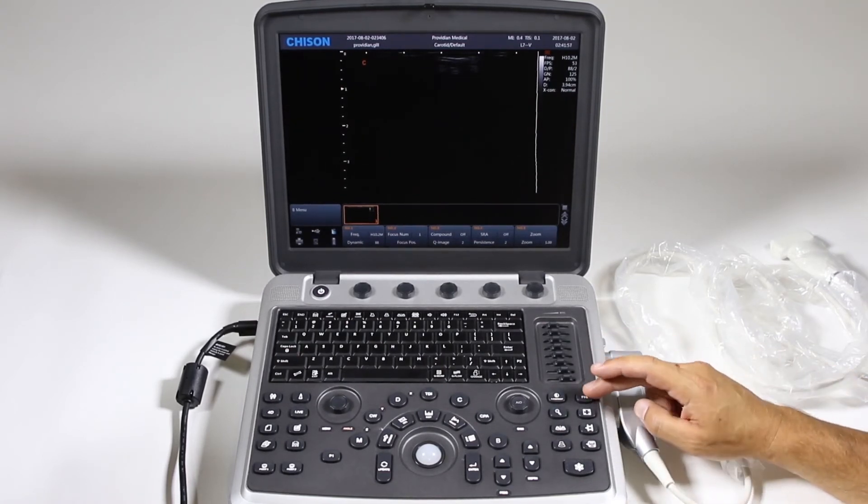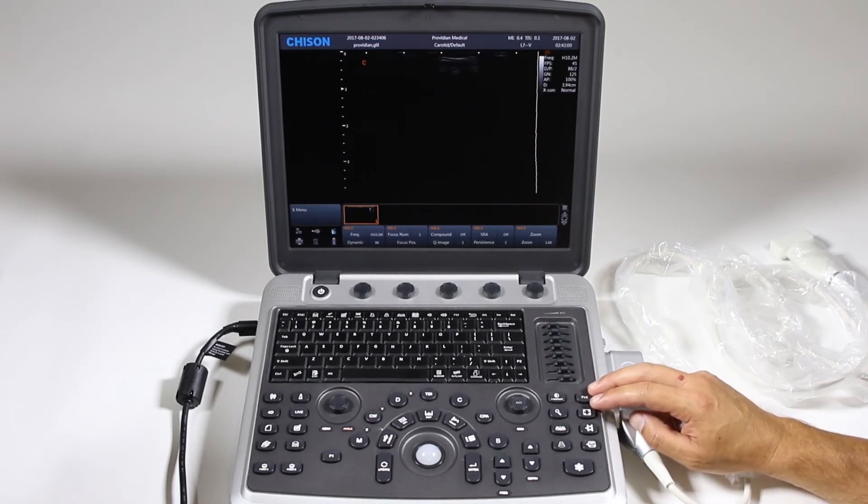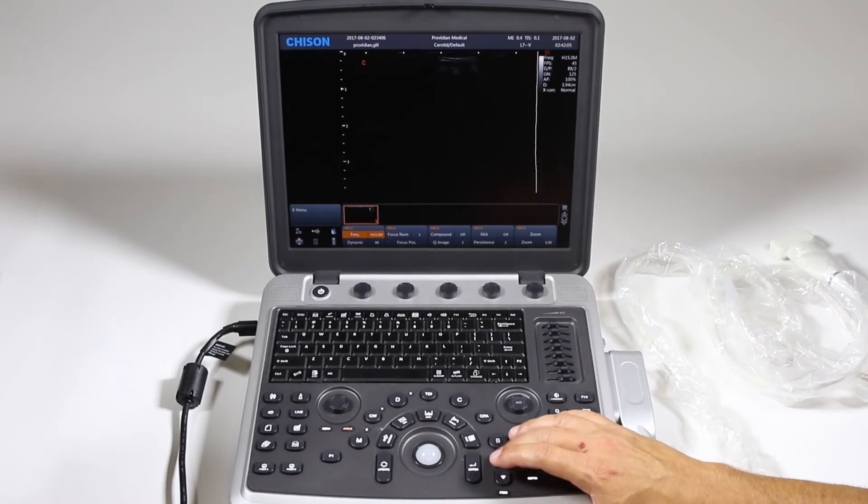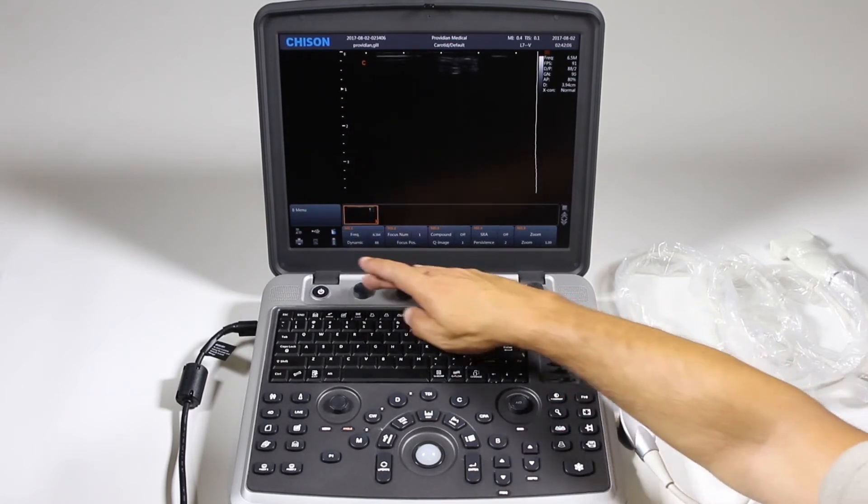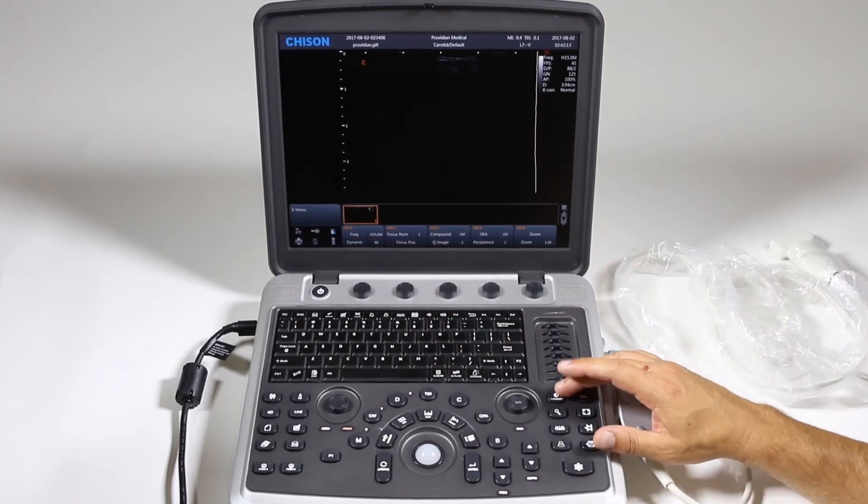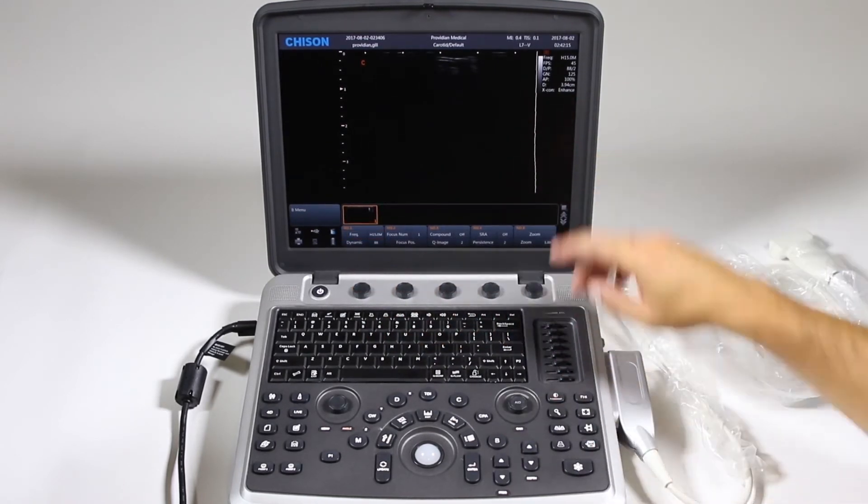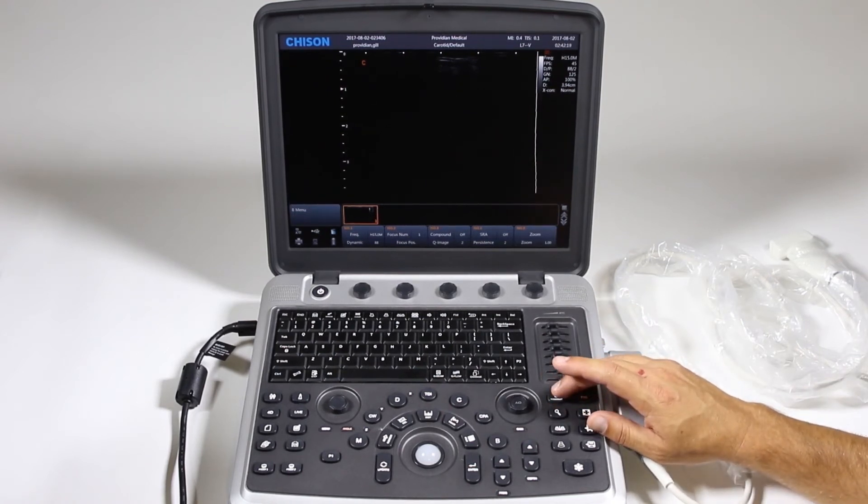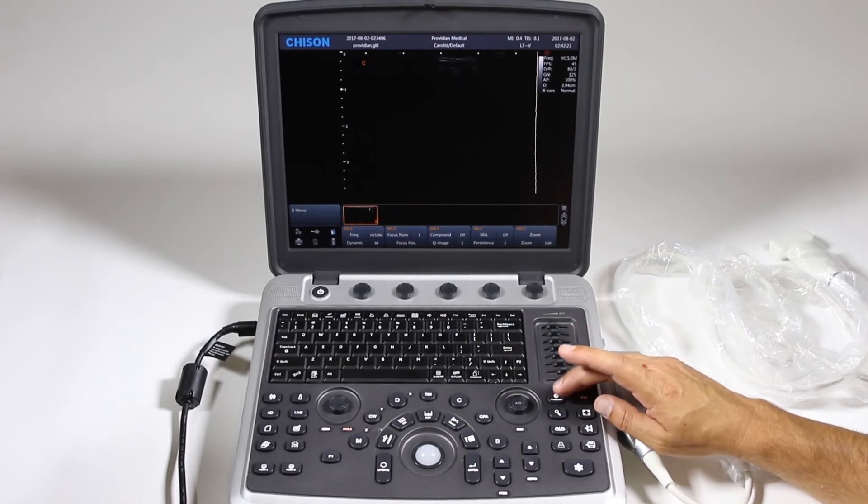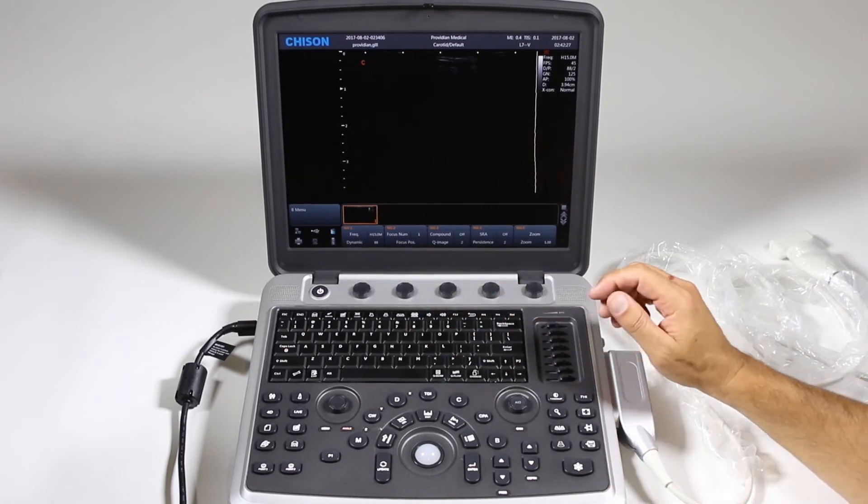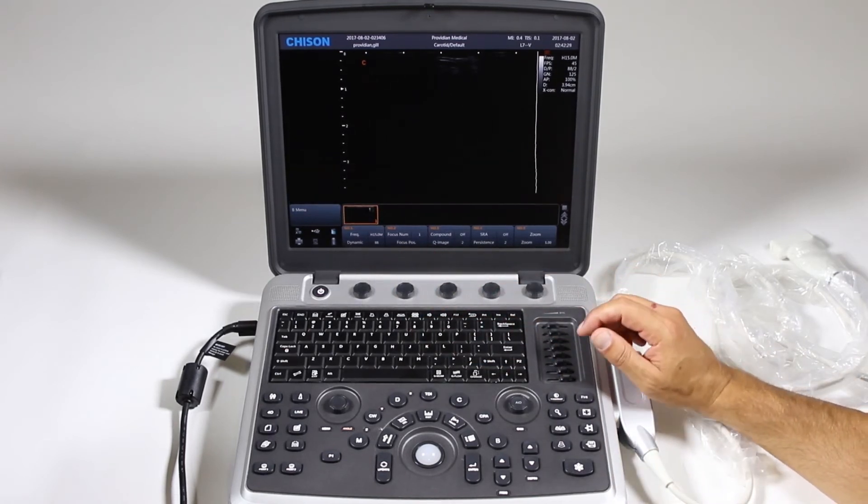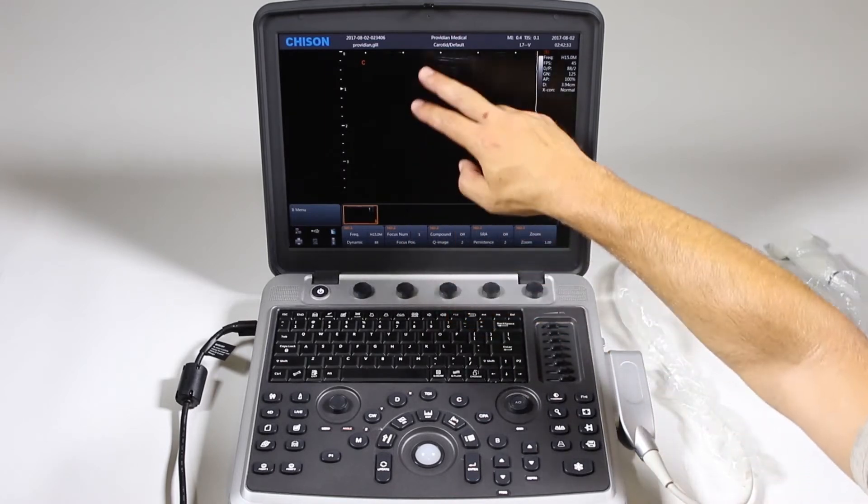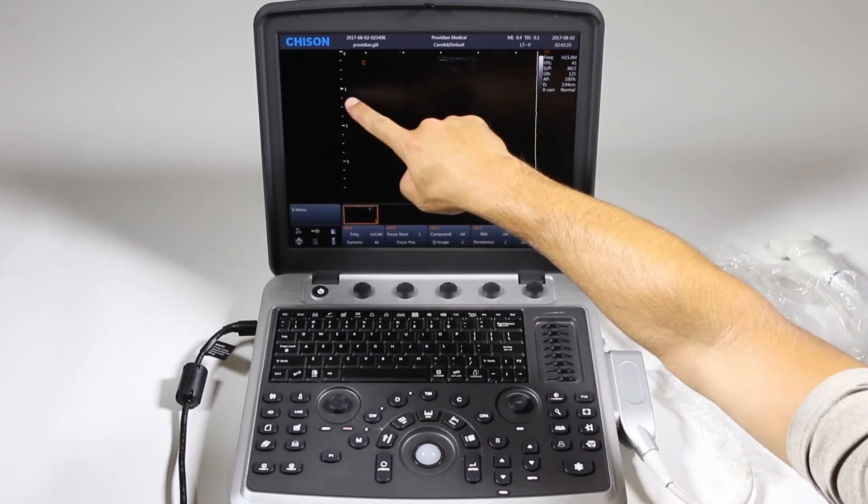This harmonics, you can turn that on and off, and that will make a fairly large difference in your image, either good or bad. But when you change the frequency, it can automatically select and deselect harmonics and fundamental frequencies as well. This X contrast, when you press it, you'll see how it goes from enhance to suppress and normal. And those can make a pretty good difference in the resolution of your image, too. I highly recommend trying that, see how it affects your image. As it is with all these image optimizations, anytime you're scanning, try different frequencies. See if the dynamic range changes. Don't forget about focal numbers and focal zones.